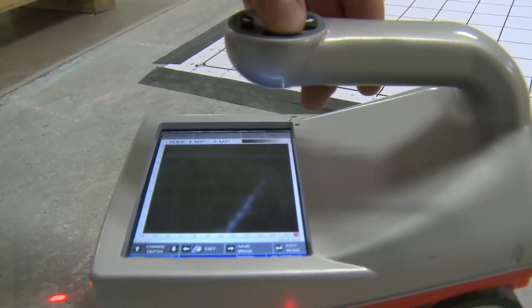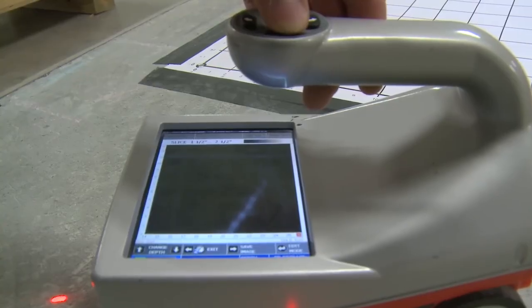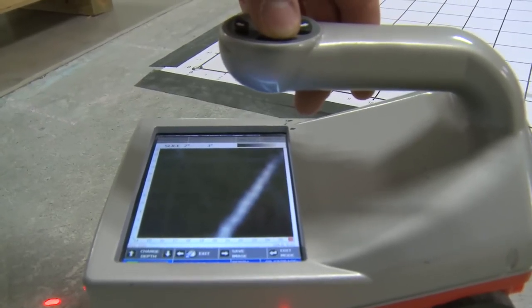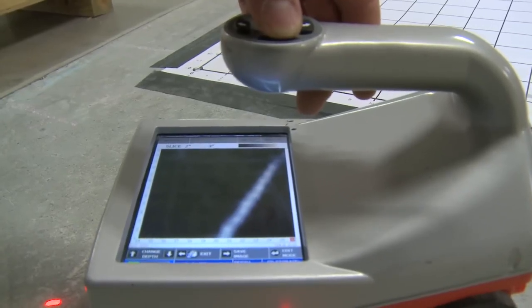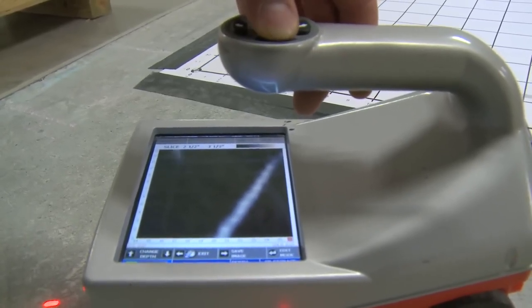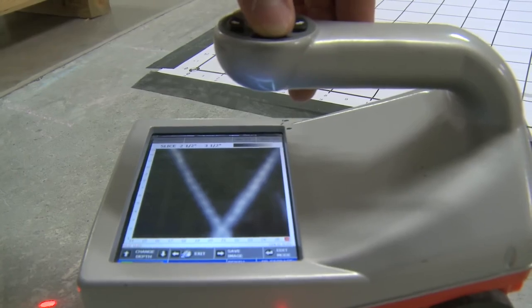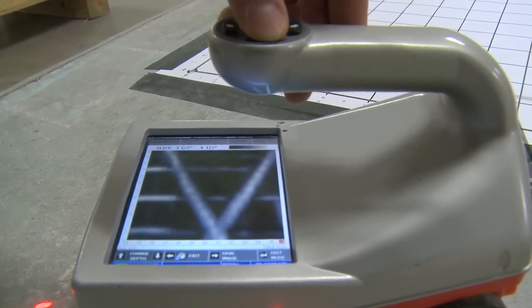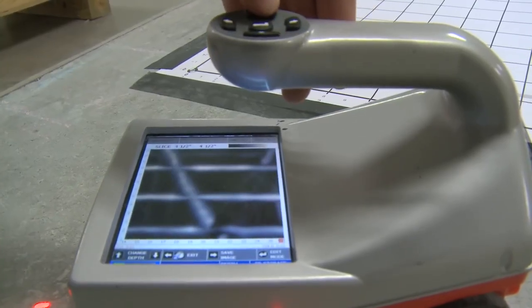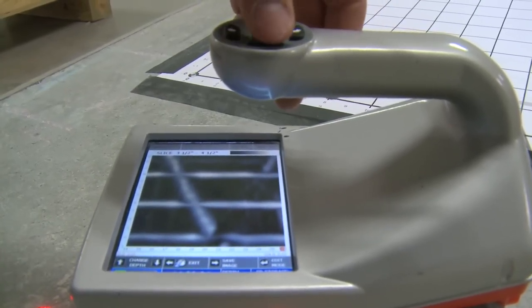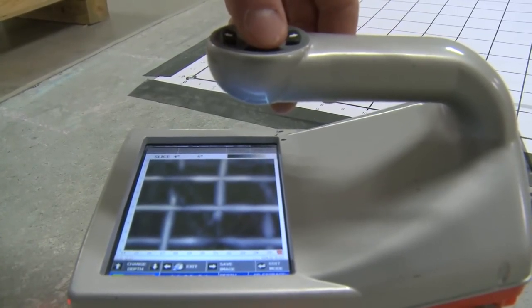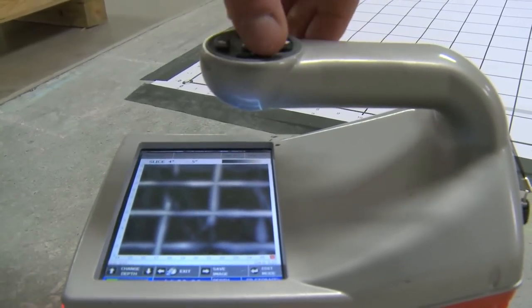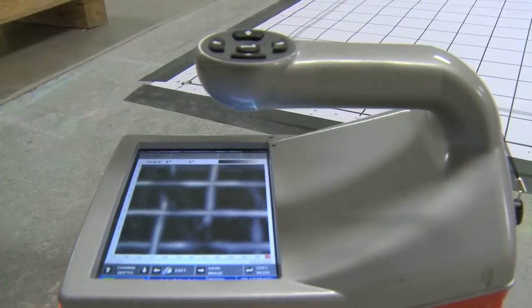And we see here that in the first few inches of the slab, there are no real targets of interest. But once we scan through enough, we're given our first diagonal line, which I know is a PT cable. Continuing down, we see our second PT cable underneath of the first. And then as we scroll through further, we see that some of our reinforcement is over top of reinforcement going in the other direction. All valuable information that you can add into your report or your survey information.